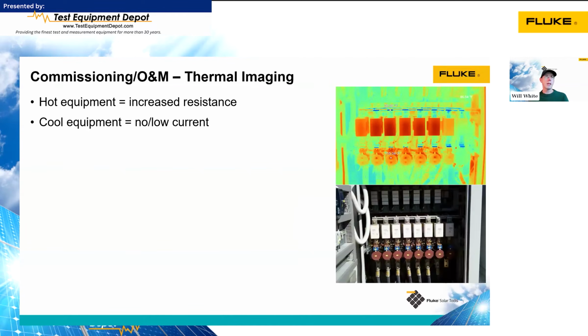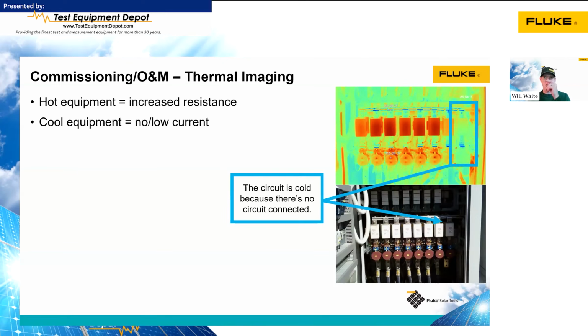When we have equipment that is hotter than other equipment, it indicates high resistance. We'll get that typically in a connector that has not been torqued down properly. Also, we can look for things that are cooler. In this example here, we've got a piece of electrical equipment. That right-hand circuit there is cooler than the other circuits because there's no circuit actually connected to that terminal. So, of course, it's not operating, so it's got a lower temperature than the circuits that are operating. Another example of this would be a combiner box where we've got a series of fuses. If one fuse is cooler than the other ones, that indicates that circuit's probably not working properly.